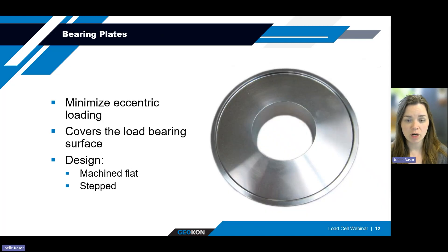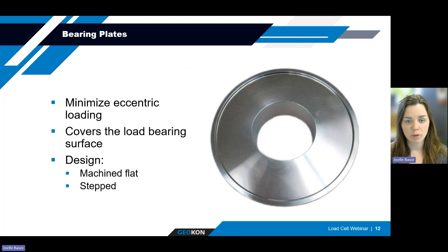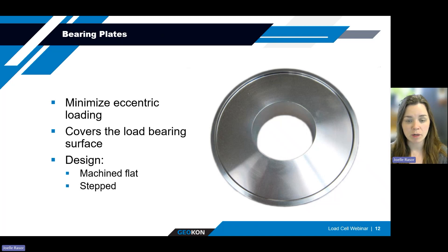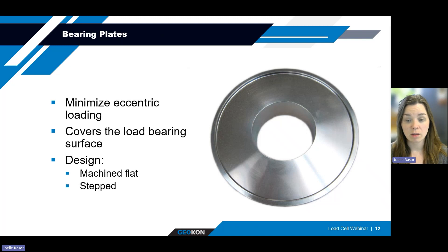To minimize eccentric and uneven loading, it's recommended that thick machined flat bearing plates and centralizer bushings, where necessary, be used as part of your test setup. Bearing plates should be machined flat and large enough to totally cover the load bearing surface of the load cell. This bearing plate is manufactured with a step to help assure that the load cell is centered properly on the bearing plate. The thickness of the bearing plate is related to the maximum applied load and size mismatch that may exist between the load cell and hydraulic jack. The greater the size disparity, the thicker the bearing plate should be. Typical thickness for a bearing plate ranges from 25 to 75 millimeters.